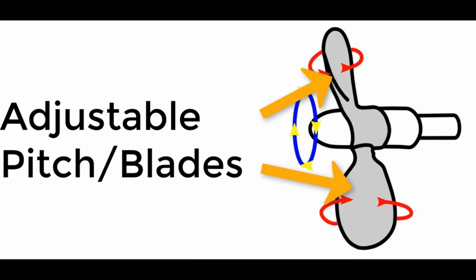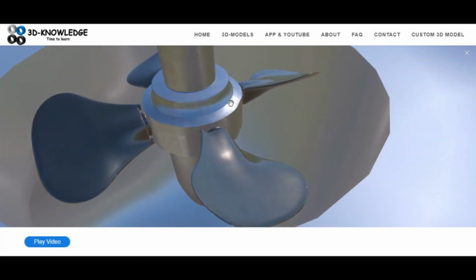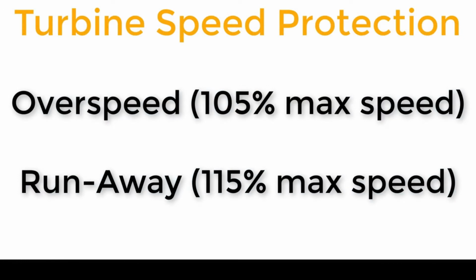It's useful because if the valves we looked at earlier did fail, we could turn the blades to zero pitch and stop the turbine rotating. The water would continue to flow past because the valves or sluice gate are broken, but at least the turbine isn't rotating uncontrollably. If it did rotate uncontrollably, it would hit an overspeed or runaway limit, sending a signal to the control unit to shut the turbine down. So you really want to control the speed properly.